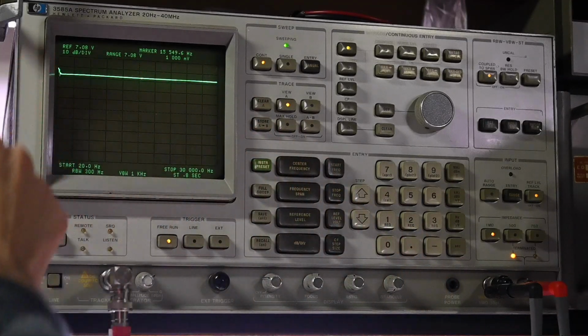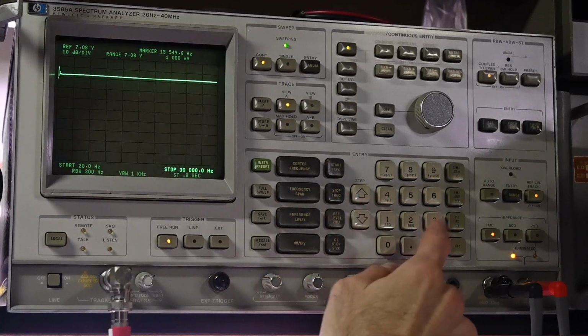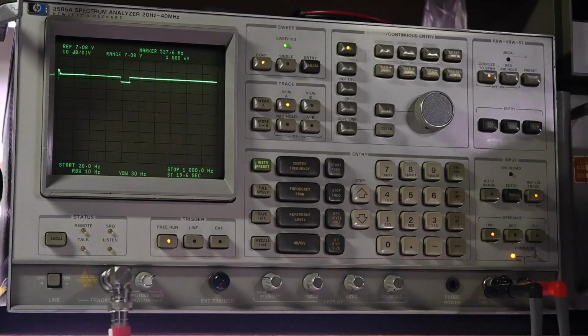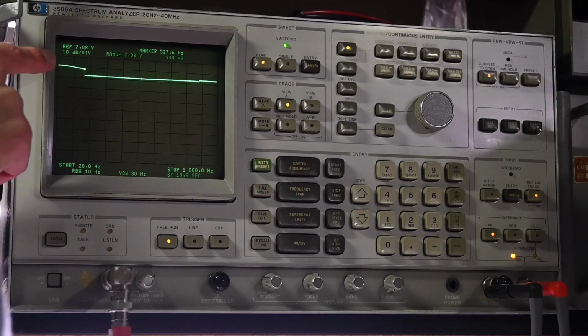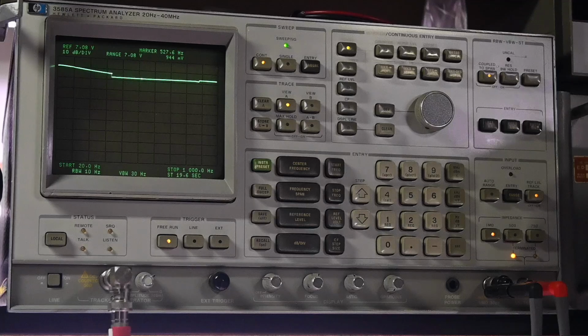So the start, again, is at 20 hertz, but I'll change the stop frequency to 1 kilohertz. Now the sweep is much slower, so we'll just let this go across here, and it's going to update. We'll just give it a moment here. The sweep time was much faster with the wider frequency range that I had when the span was wider. Okay, so it's completed the complete sweep now. Now I'll change the bass, and I'll turn the bass all the way up. Give it time to do another sweep and see what we have. Now we can see that it does in fact increase those lowest frequencies.